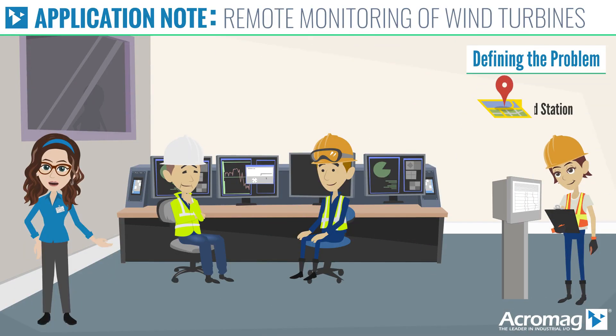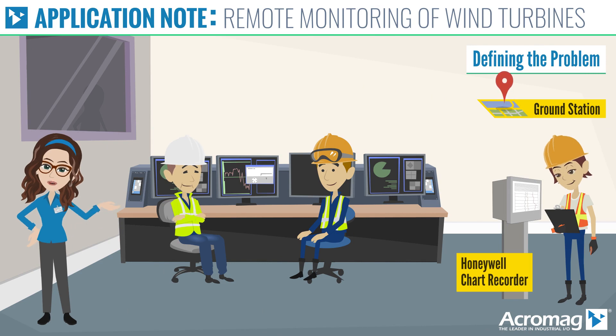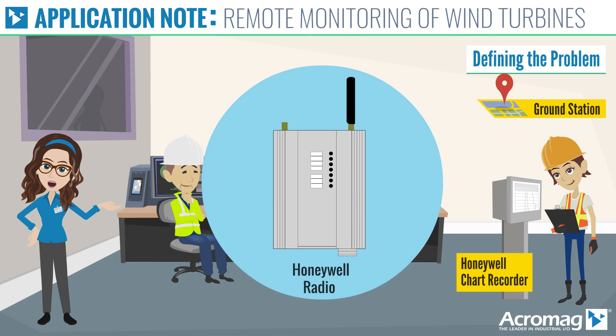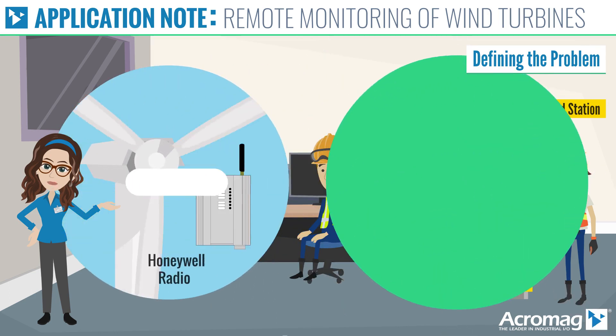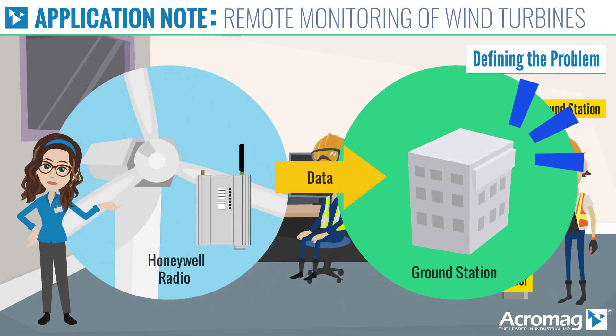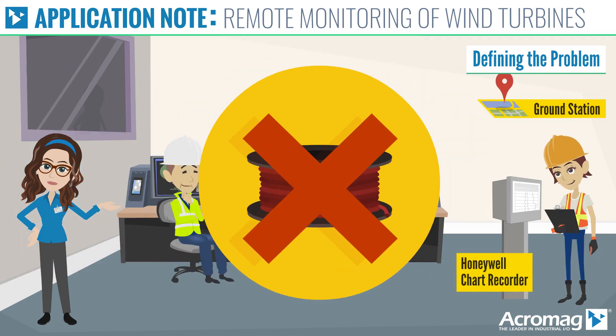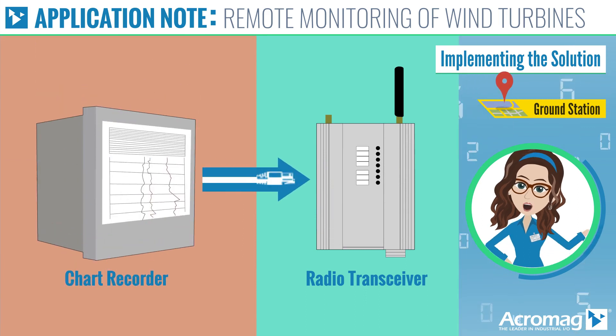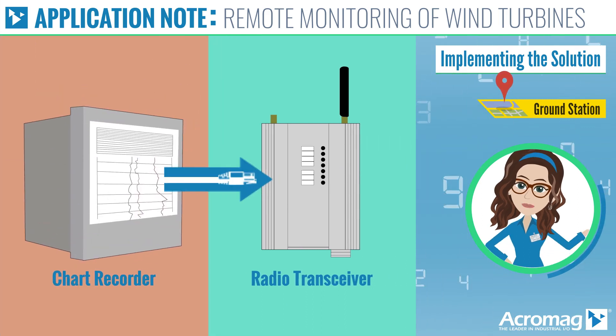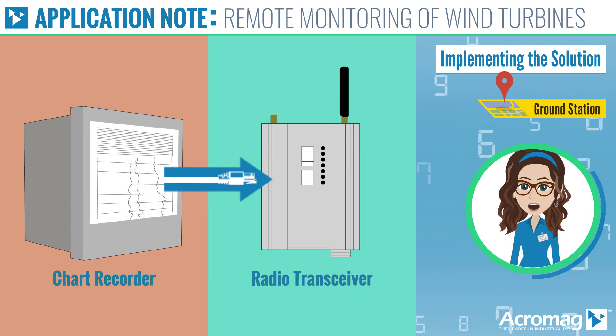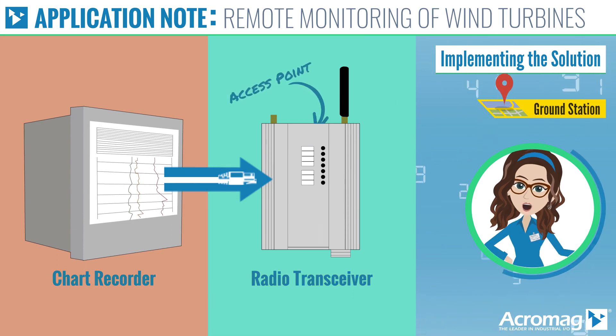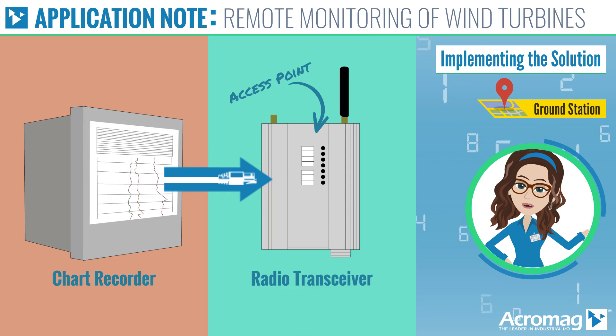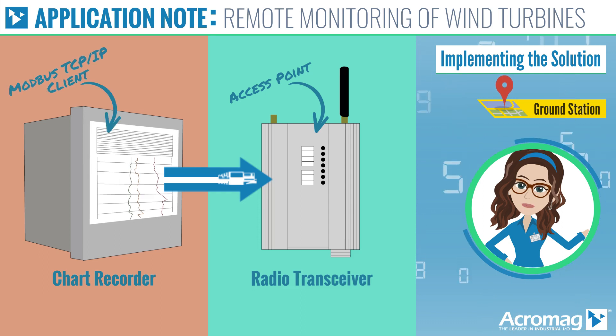The ground station is equipped with a Honeywell chart recorder that also serves as the Modbus client. The system will use Honeywell ethernet radio links to send information from the wind turbine head to the ground station, thereby eliminating the need for long ethernet cable runs. At the ground station, connect the Honeywell chart recorder to the ethernet port of one of the Honeywell radio transceivers. Configure the radio transceiver as an access point and set up the chart recorder as a Modbus TCP/IP client.